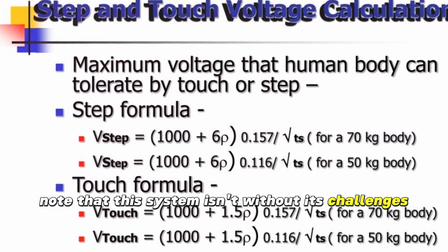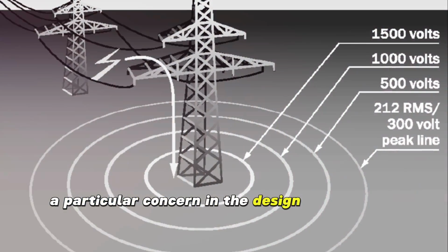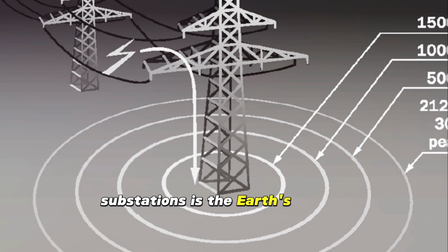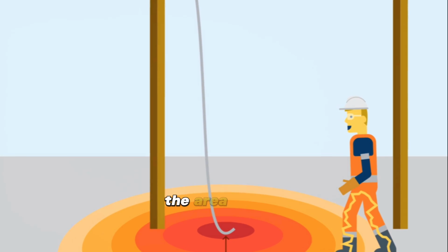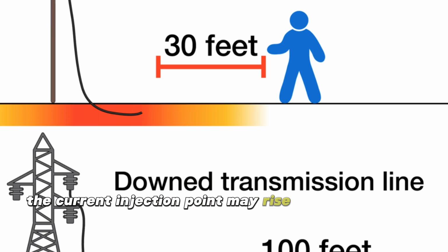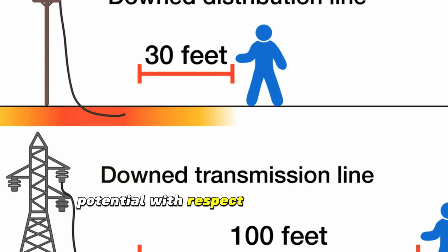Now, it's important to note that this system isn't without its challenges. For example, a particular concern in the design of electrical substations is the Earth's ground voltage potential rise. The area around the current injection point may rise to a high voltage potential with respect to distant points.